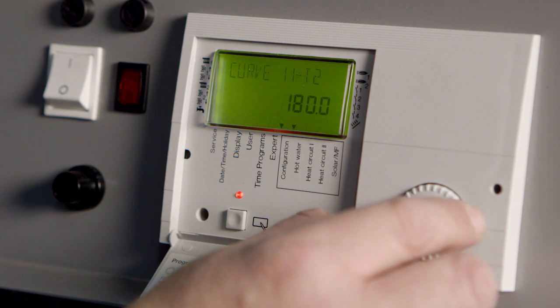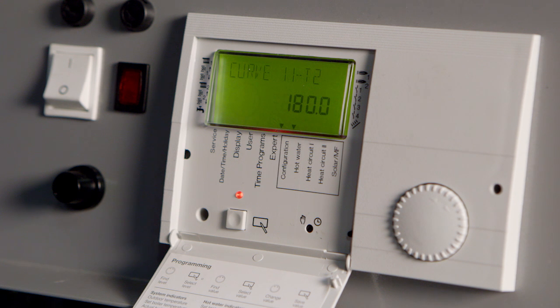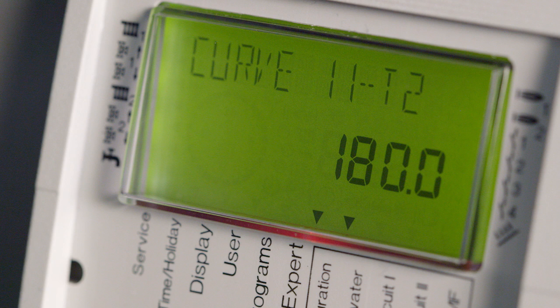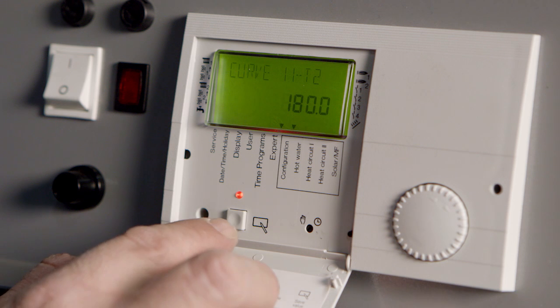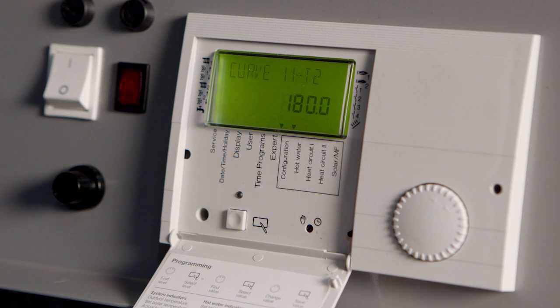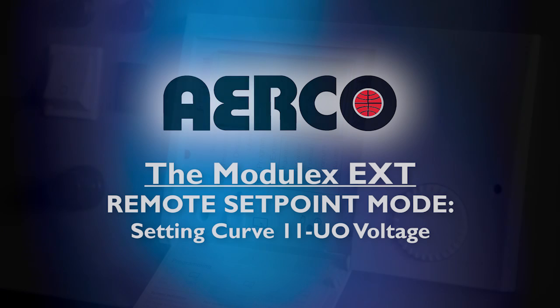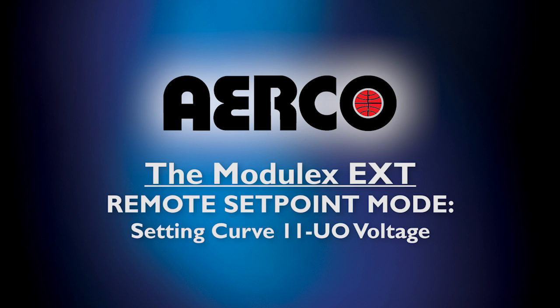Enter the high set point temperature for T2. This value will correspond to what you set for U2. With this limit displayed, press the program key to set the T2 temperature. UO is a voltage that will turn off the boiler. This means you should set your UO voltage level below the limit you set for your U1 voltage.